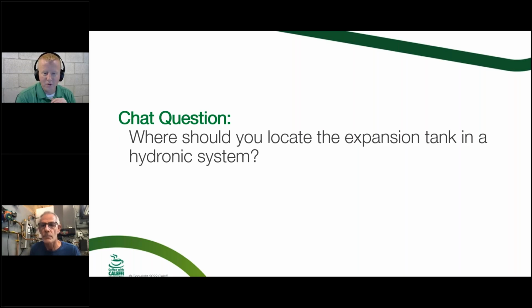We got one person saying before the boiler. I presume you're looking for the cooler temperatures there, the suction side of the circulator, lowest pressure, highest temperature. Yeah, some great answers in here, guys. Yeah, I wanted to make sure you were still awake there.